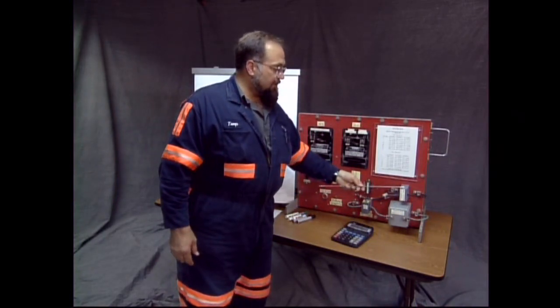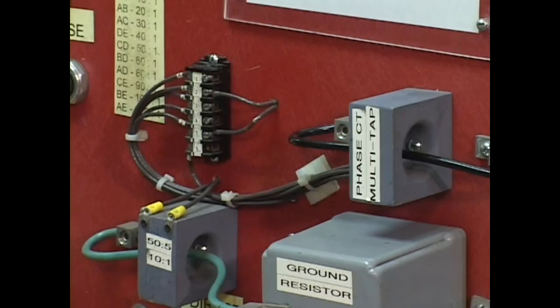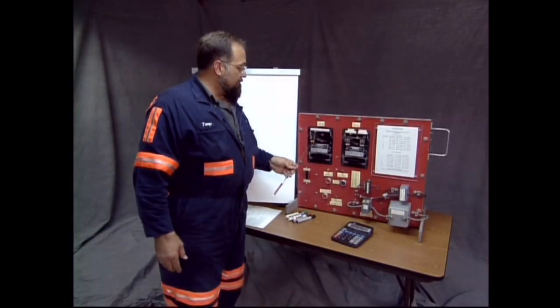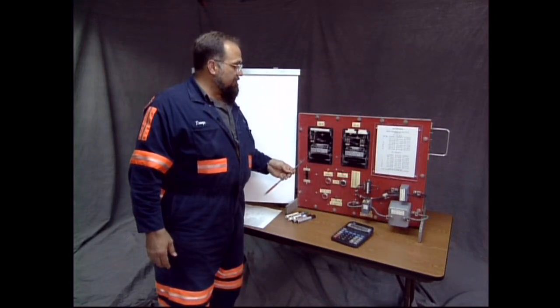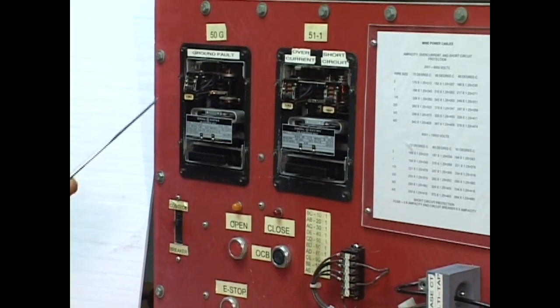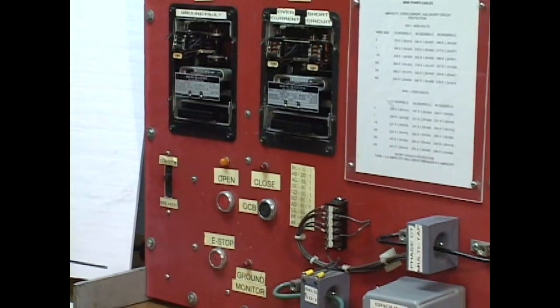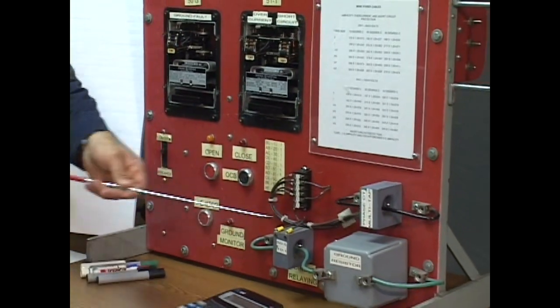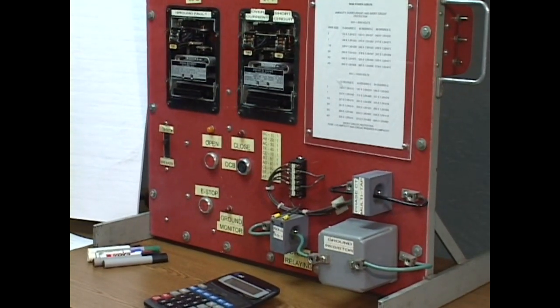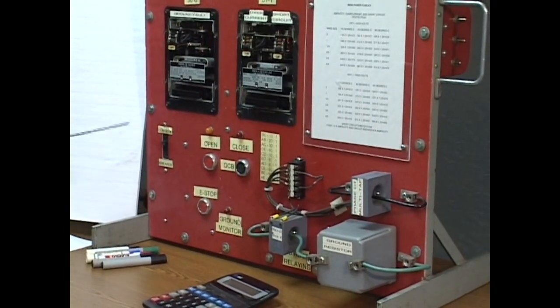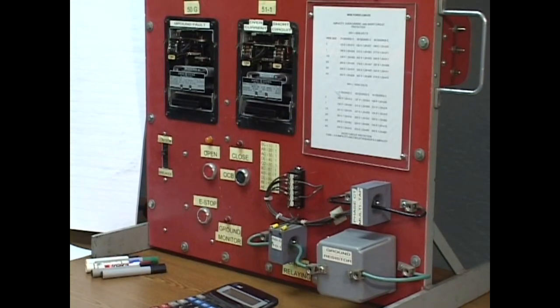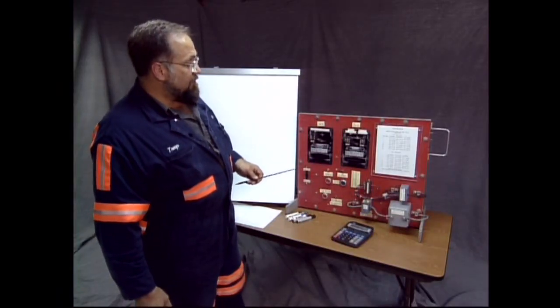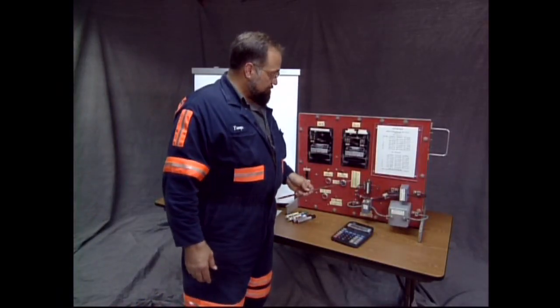So, the ampacity of the secondary, 5 amps. That gives us our maximum overcurrent setting, a tap of 5. And the maximum setting for this is 1/2 the value, the current ampacity of your ground resistor. 1/2 of that. That's for ground fault. Now we've got a basis there to work on.